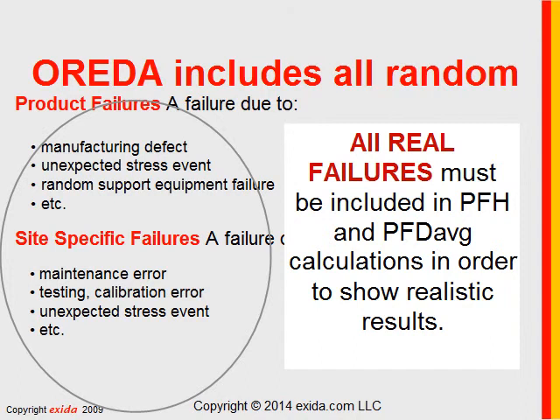After traveling to Norway and attending a safety seminar where OREDA versus FMEDA was debated, it was very clear to me that OREDA felt strongly that all real failures must be included in PFH and PFD average calculations for realistic results. This means both product-related failures like manufacturing defects, design weaknesses, unexpected stress events, failures of random support equipment, and site-specific failures like maintenance errors, testing and calibration errors, and exceptional high stress events.